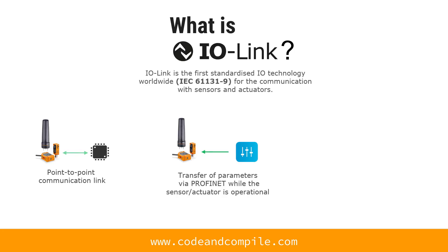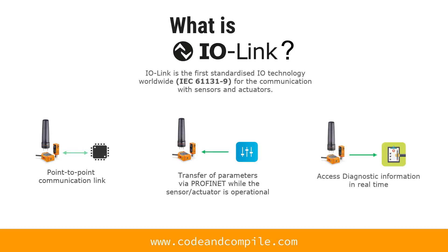The second feature is transfer of parameters via Profinet while the sensor or actuator is operational. So you don't have to halt your machine to parameterize your sensor — you can do it while the machine is running. The third amazing feature is you can access diagnostic information in real time, so if your sensor fails or something is happening, you can access the diagnostic information and replace the device without any breakdown.